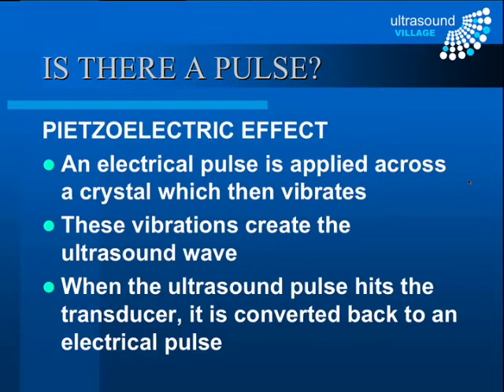Going into more detail on how the machine works: a pulse is generated by the piezoelectric effect. An electrical pulse is applied across a crystal, making it vibrate, and those vibrations create the ultrasound wave. Similarly, in the reverse effect, when an ultrasound pulse hits the crystal in the transducer, it vibrates and the crystal creates an electrical pulse.